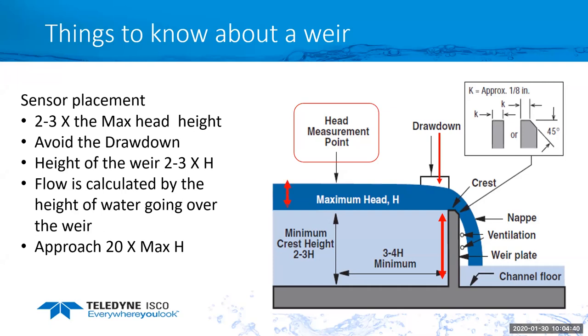Now, as far as when measuring flow or head height with a weir, we are concerned about the water going over the top of the weir. So where it says the maximum head height, that's the water that we're concerned with going over. So when you do a level measurement, you determine what the weir height is. You would measure the overall depth and then subtract the height of the weir wall. And then that would give us the level of the flow that's going to go over the top of the weir. As far as the straight run in front of a weir, it should be 20 times the maximum head height that you expect to see over that weir. And the more straight run of pipe or channel you have upstream, the better, because what we're looking for is uniform flow going across this weir.